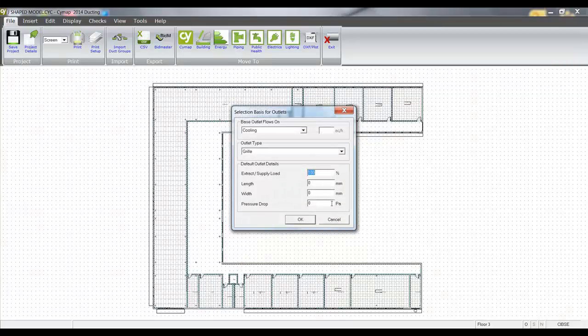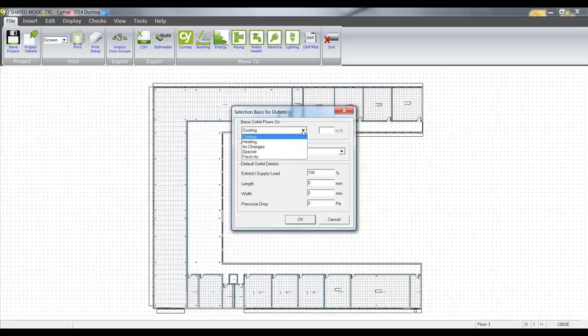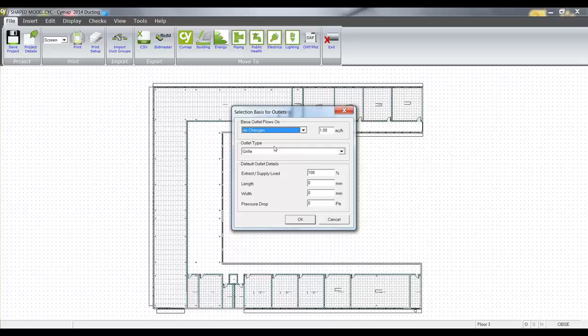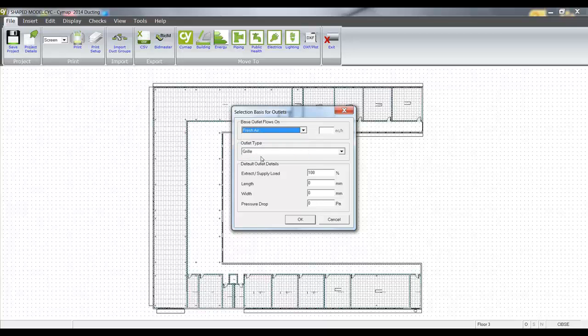The next option open to me is the basis of the calculation. I might want to base that on cooling or heating if it's an all air system. Air changes would allow me to stipulate the extract rate or supply rate to a room in terms of air changes an hour. Or I could base that on fresh air for occupancy. If we're providing air to these spaces for occupancy as a minimum fresh air requirement, we'll go with fresh air.